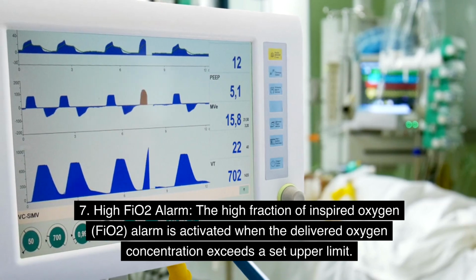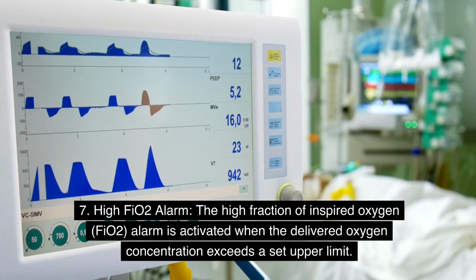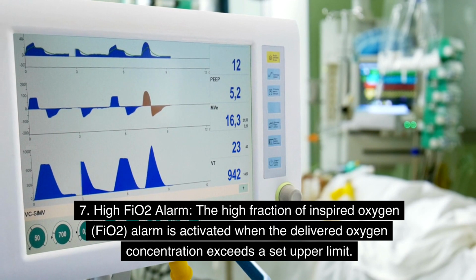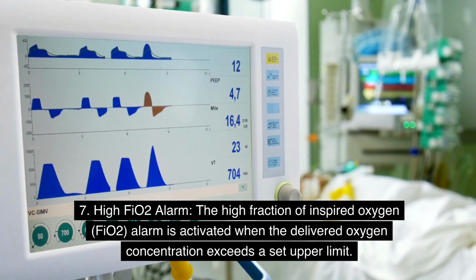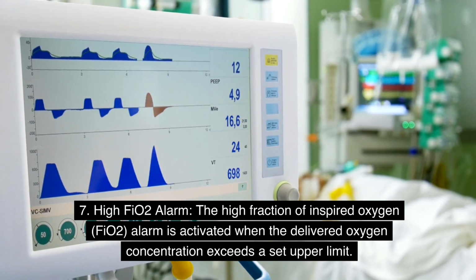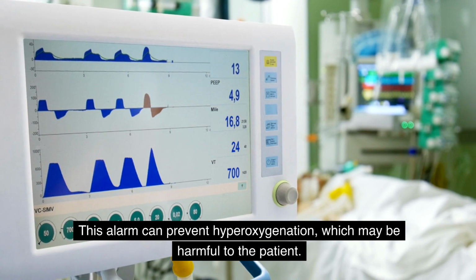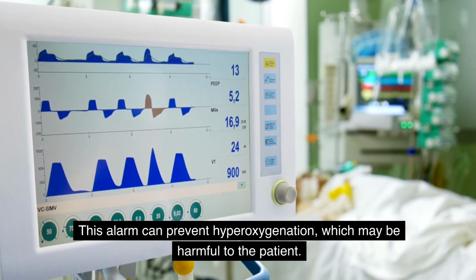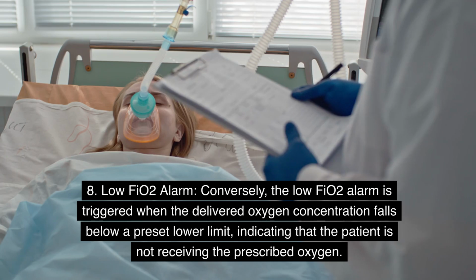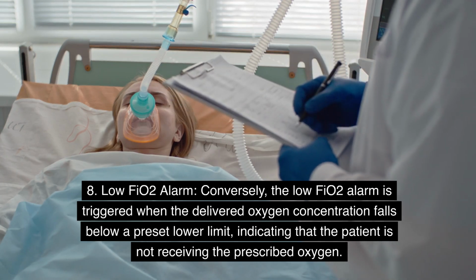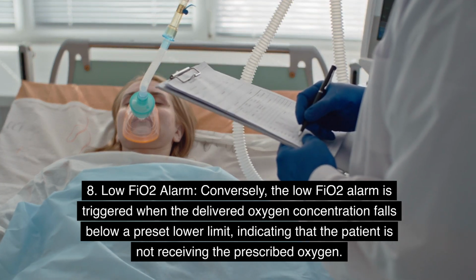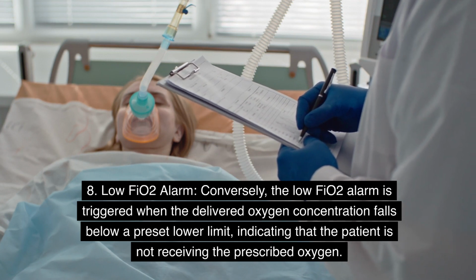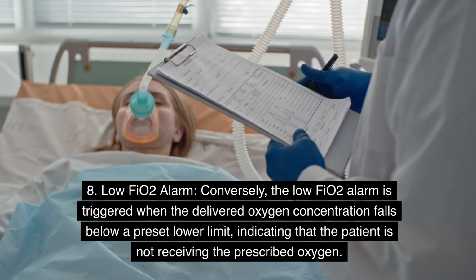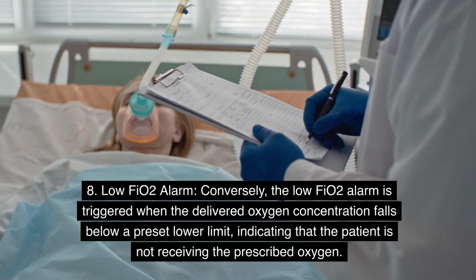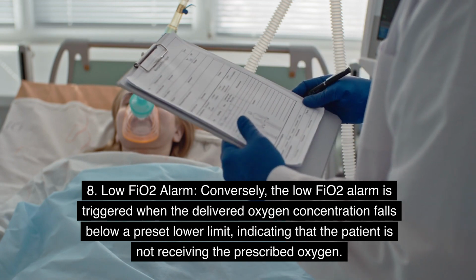7. High FiO2 alarm. The high fraction of inspired oxygen, FiO2, alarm is activated when the delivered oxygen concentration exceeds a set upper limit. This alarm can prevent hyperoxygenation, which may be harmful to the patient. 8. Low FiO2 alarm. Conversely, the low FiO2 alarm is triggered when the delivered oxygen concentration falls below a preset lower limit, indicating that the patient is not receiving the prescribed oxygen.